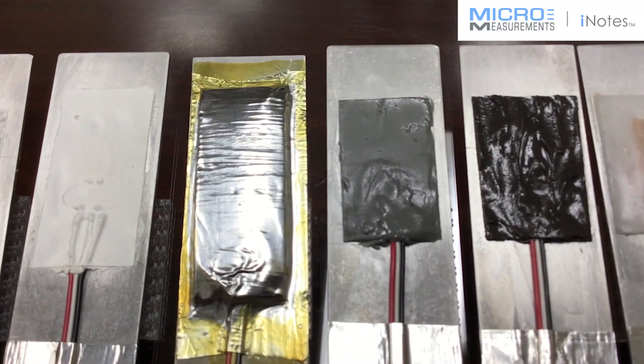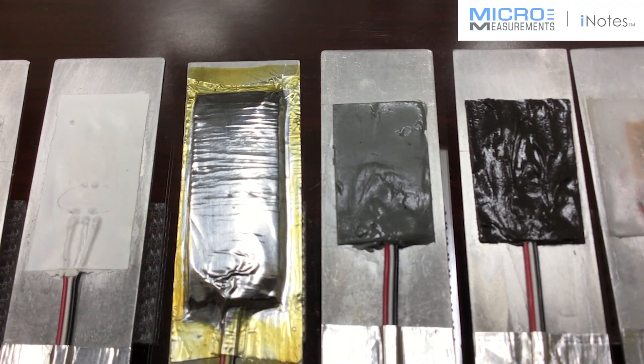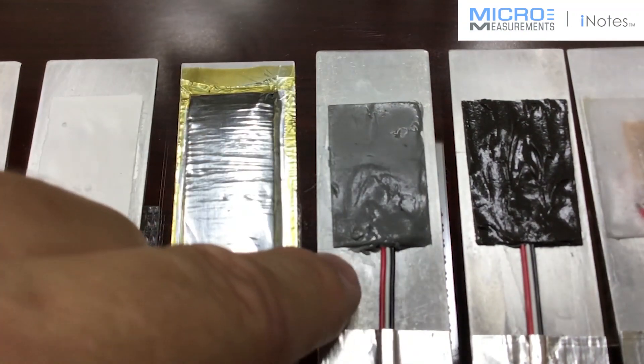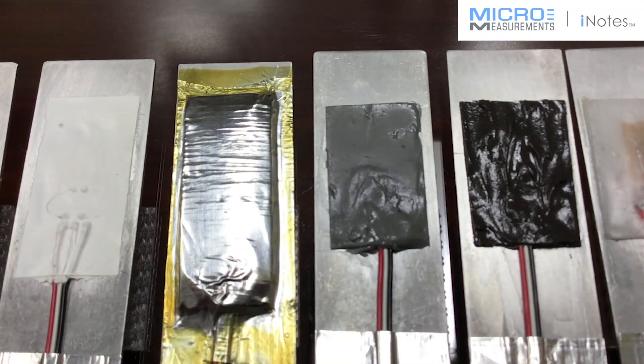So if you're protecting a strain gauge based load cell and you're looking for something that won't stiffen the structure, this is a pretty good coating to choose. Oftentimes our customers will put this on and then they'll apply something else over the top of it just to help give it better mechanical protection, but from a moisture protection standpoint it's really good.